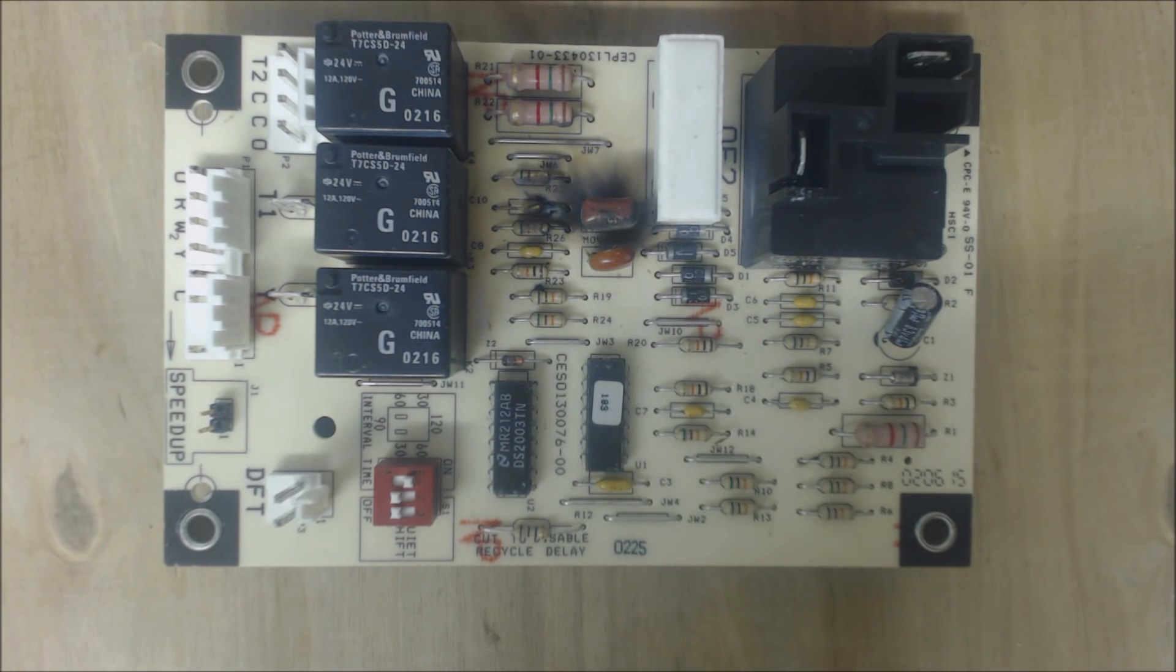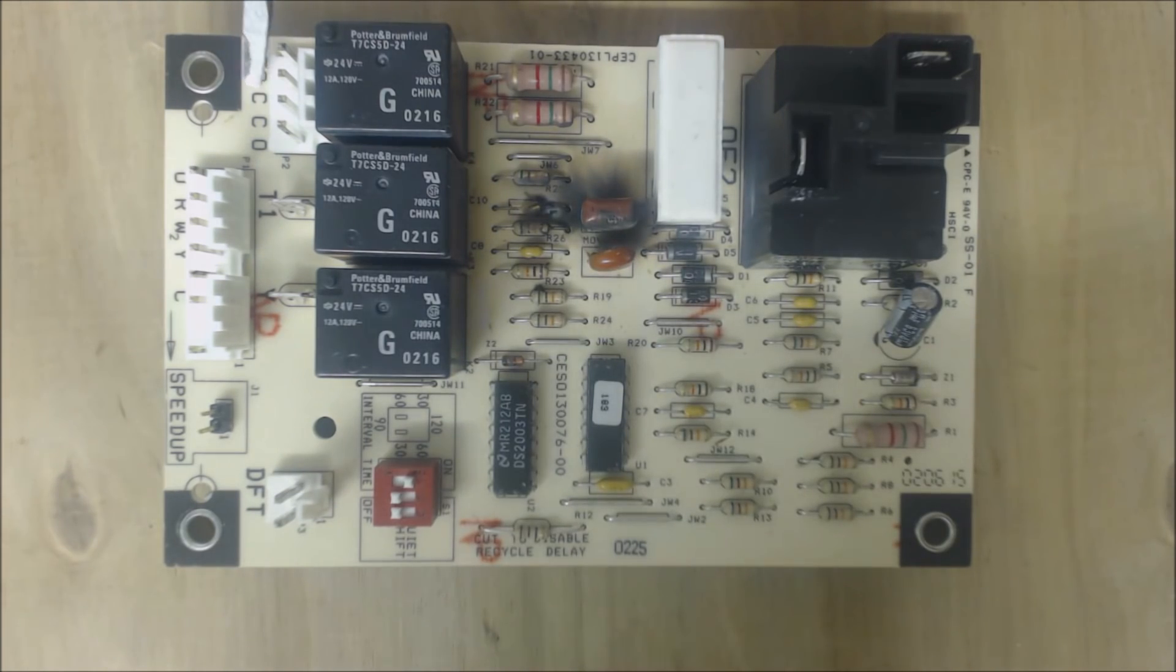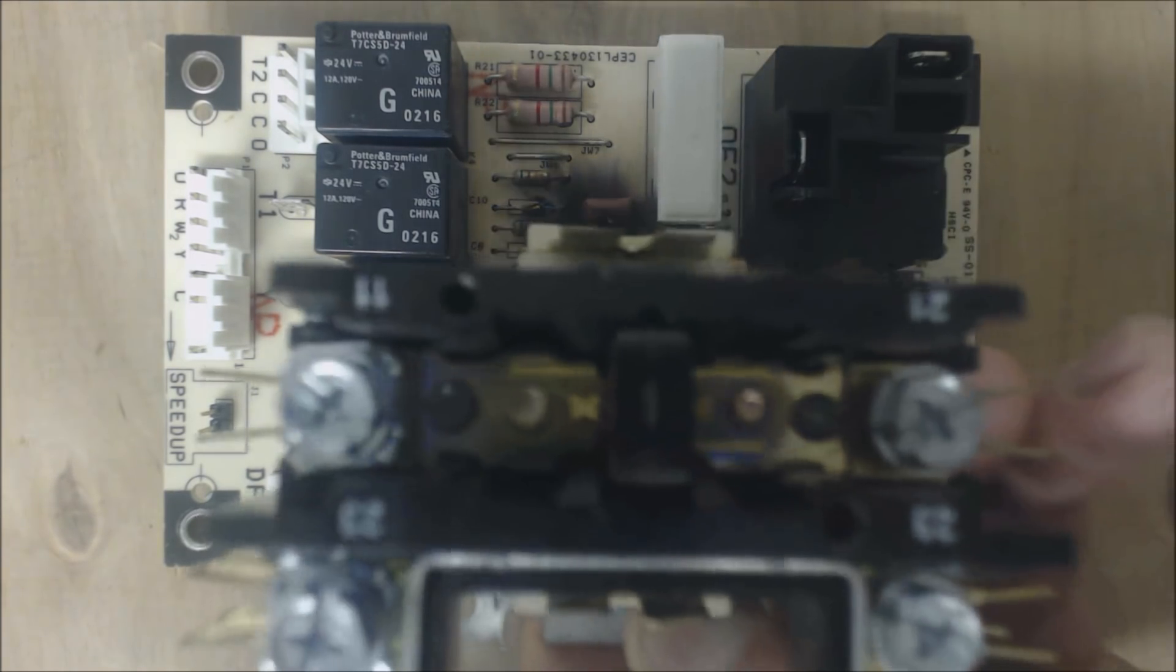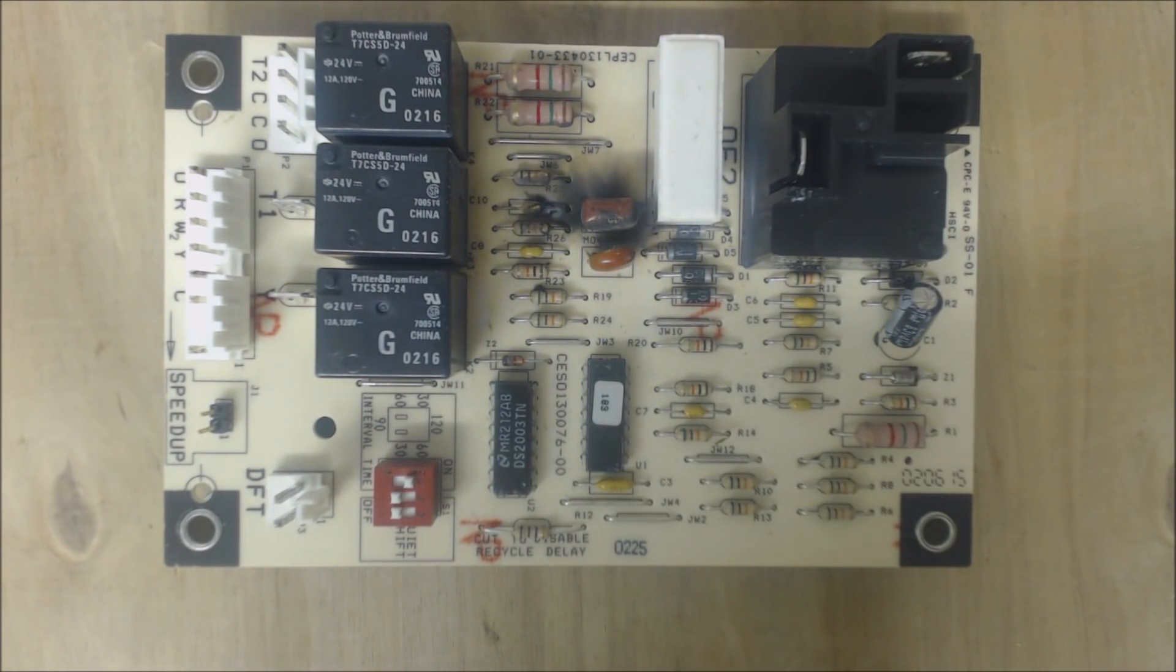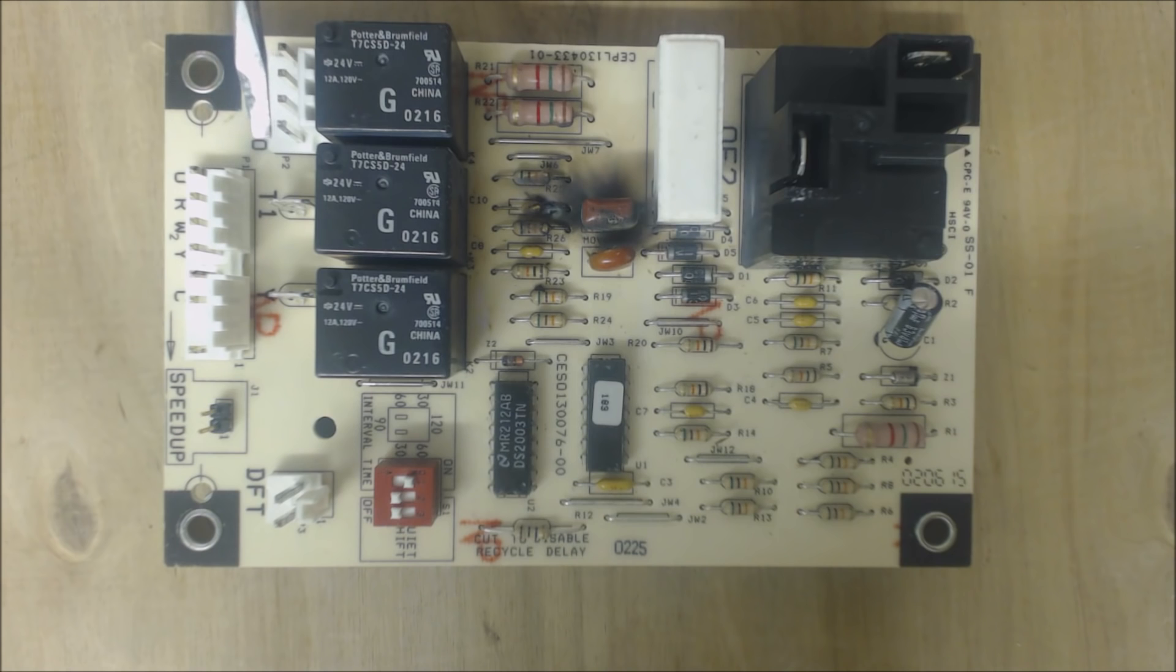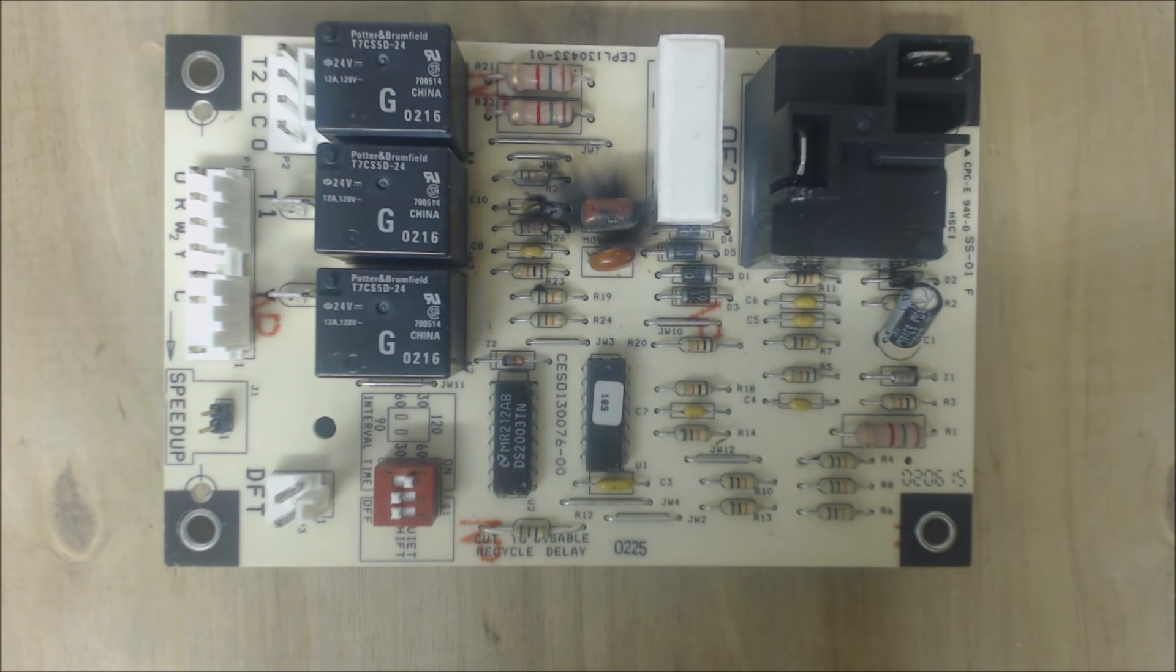The next thing you have is T2. T2 and common goes and powers the contactor. It comes in here and then it exits on this side. And when it exits, it comes back through the C. So this is powering the heat pump to the on position. Then down here, you have the O that powers the reversing valve and C is where it comes back. So it goes from O here out to the reversing valve and back through the C terminal.